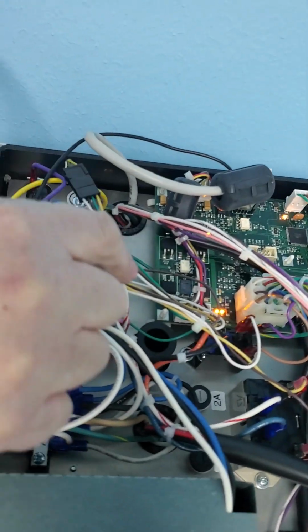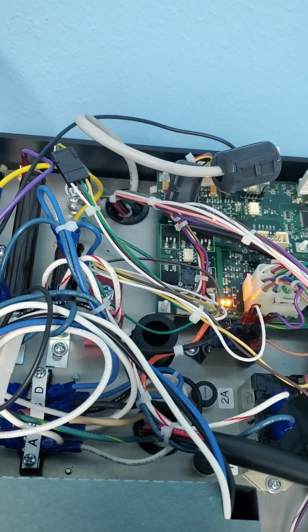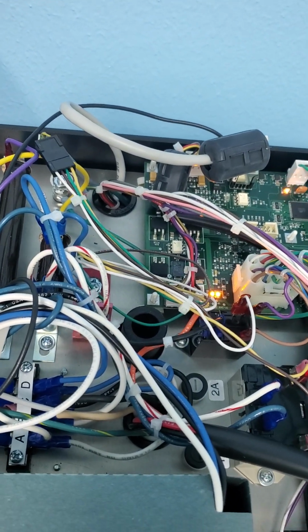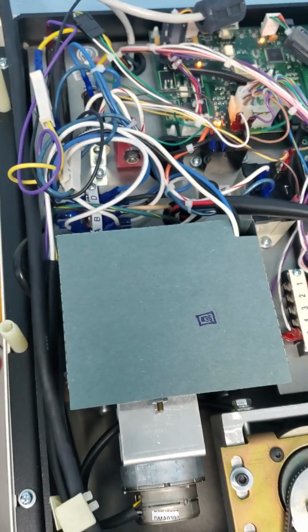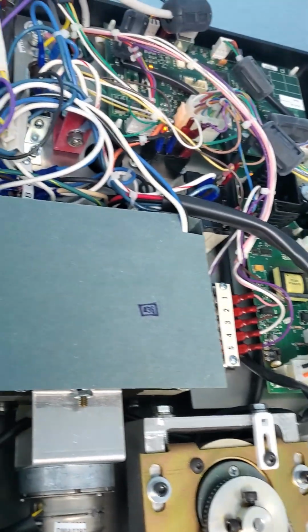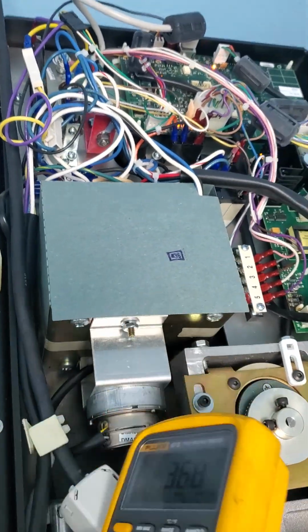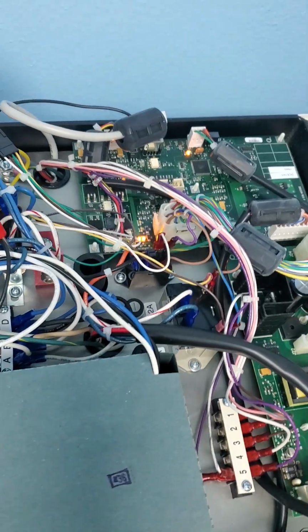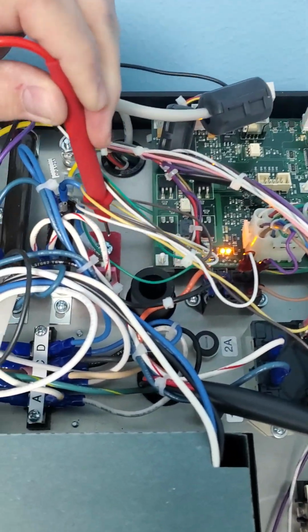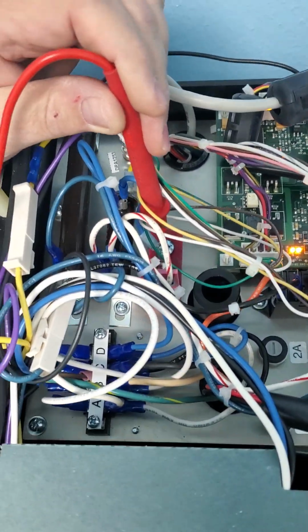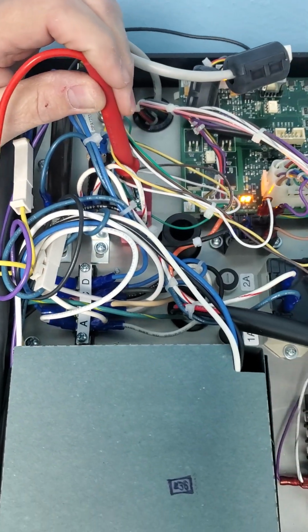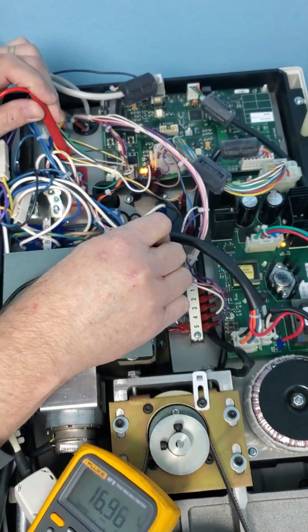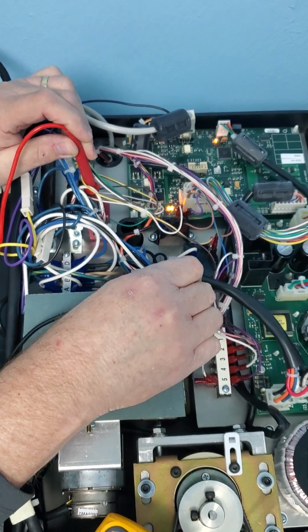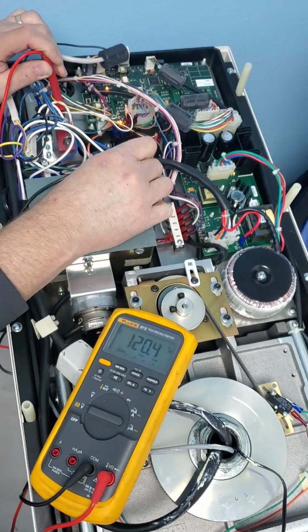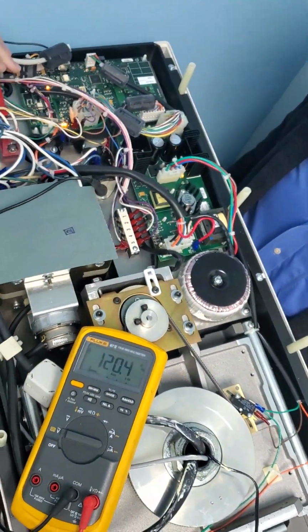Right here, that's on this red. The tip of that, where the wire screws onto it. You measure between there and a ground point on the back plate. Where's the triangle? It's right here. That one. Okay, I see it. Yeah, it's in that heat sink. You put it on the screw, and you put the other one in a ground point. Okay, there you go. We should be reading 89, and we're measuring 120.4.